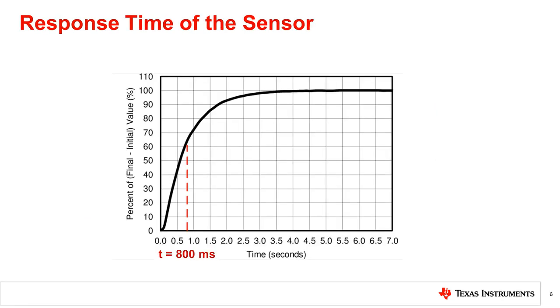When designing systems which can change temperature quickly in a fault condition and need to be protected, it is necessary to consider the response time of the temperature sensor. This response time relates to the potential heat rise time during a fault condition because this allows for the system to react before the thermal limits of the system components are reached, leading to damage. The response time is defined as a time for a temperature sensor to reach one tau or 63.2% of the total difference between its initial and final body temperatures. In the example here, you can see a thermal response of 800 milliseconds.